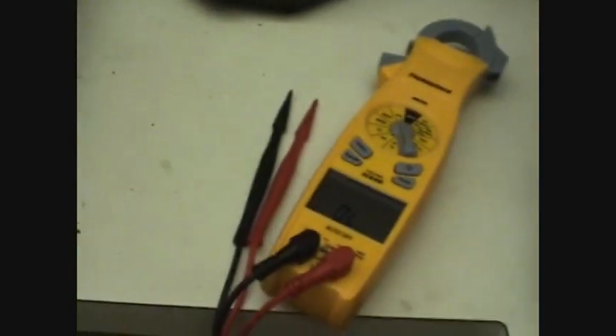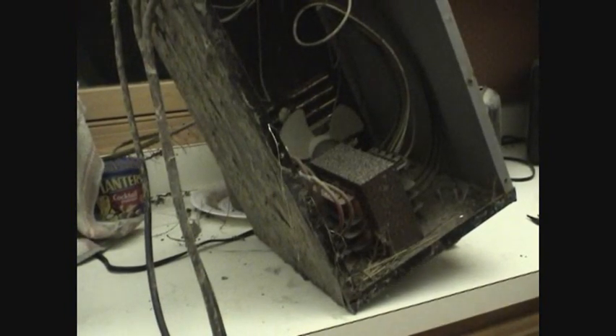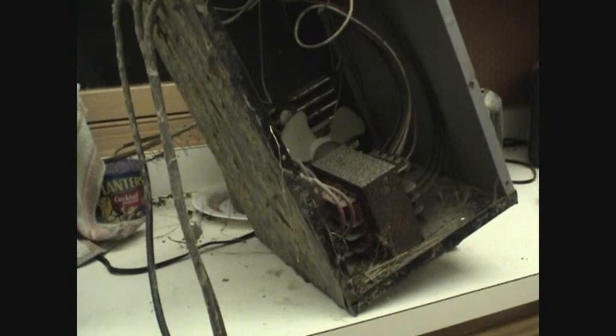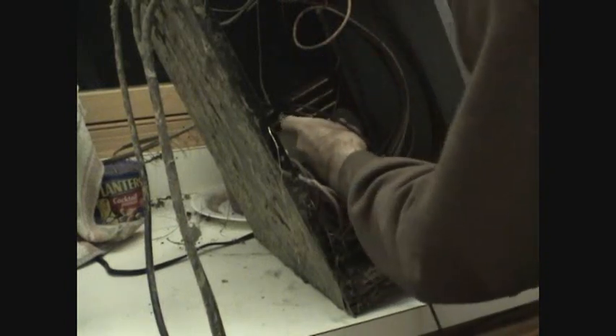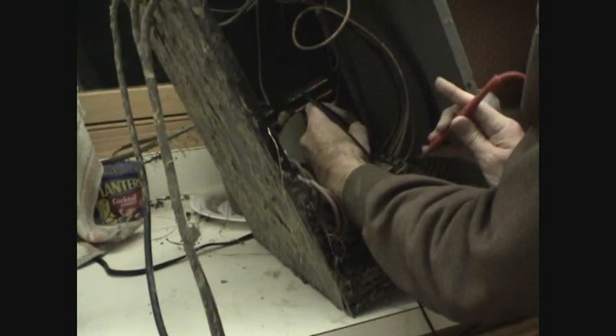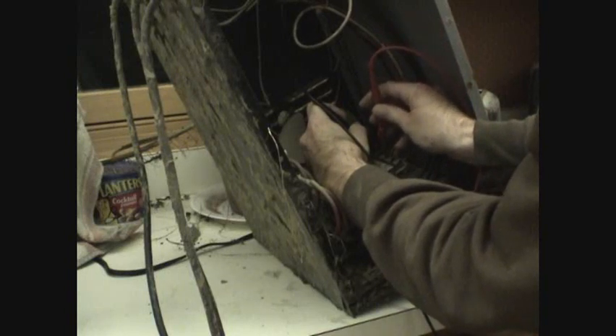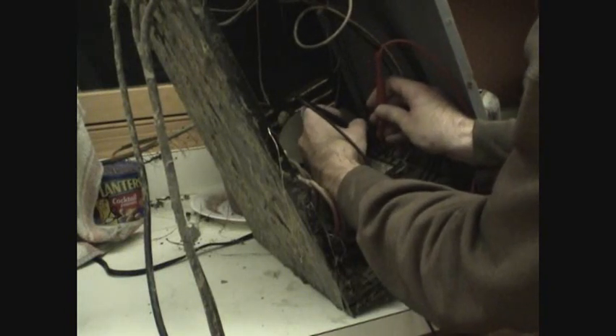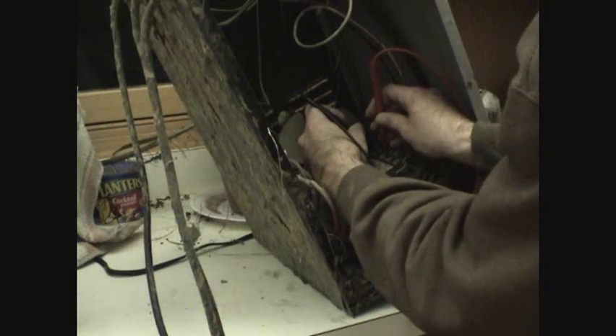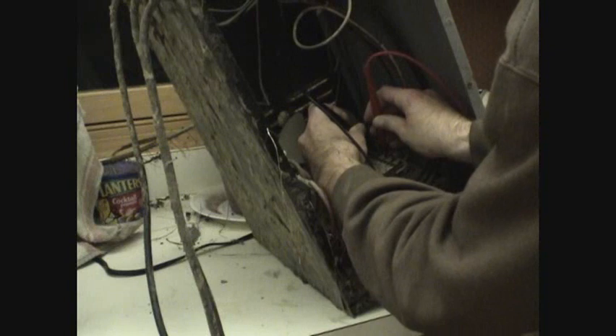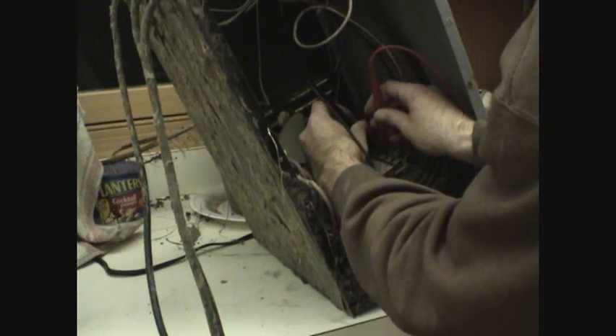I'm going to keep a lead on the common on the transformer and just make my way down and test each one, and you guys should hear a beep with each test. If you guys can see, we'll put this on common. Now we'll go to our first one. Just making sure the meter's on. This thing is so crusty, it's hard to get a good connection here.